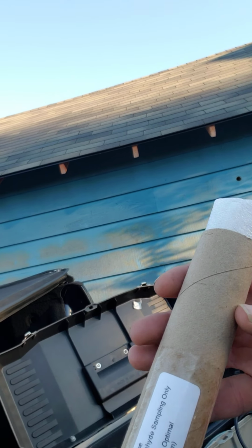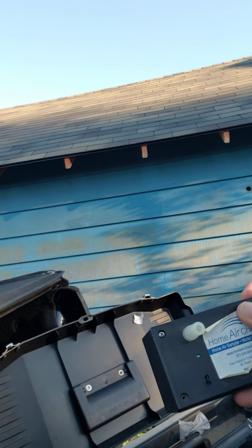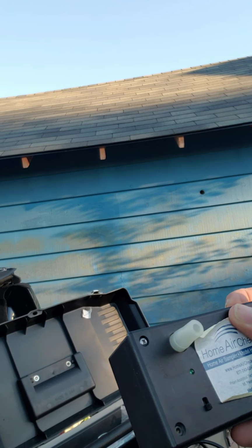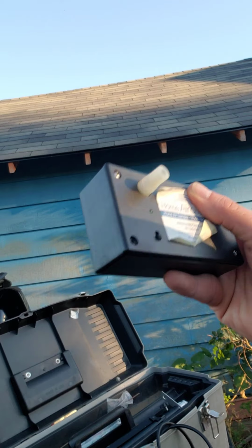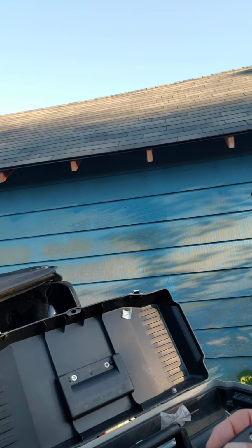We also use some tubes. The tubes are for checking for formaldehyde. This is a formaldehyde sampling tube, which plugs into one of these little air pumps. This air pump runs for formaldehyde for 25 minutes, and then they can tell what the level of formaldehyde is. If we're looking for VOCs or chemicals, we run it for an hour and a half through the same type of tube, but it's designed strictly for volatile organic compounds.